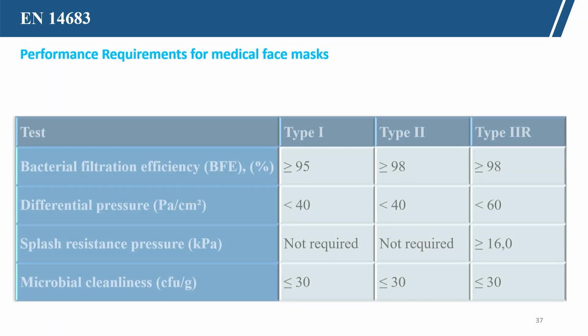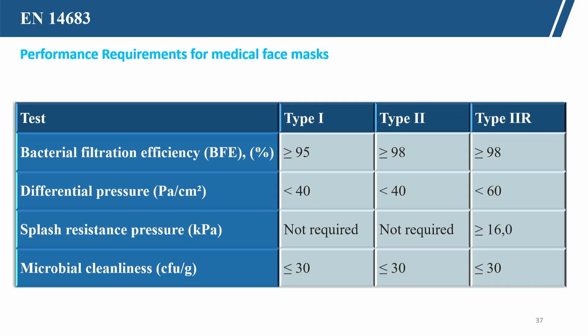So, as per the EN 14683, the performance requirements of face masks are as follows. BFE, bacterial filtration efficiency, for type 1, type 2 and type 2R. Type 1 is more than 95%, type 2 is 98%, and type 2R is again 98%.